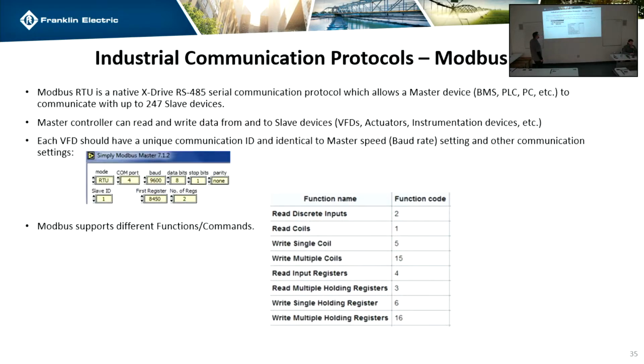All right, so if you're using Modbus, anybody here use Modbus on a drive? Okay. If you're dealing with someone that's telling you the drive's Modbus doesn't work, they're wrong. It works just fine. It's wiring, or it's the actual program they're using. If you call our tech support, they're not communication guys either. They're going to read out of the manual.